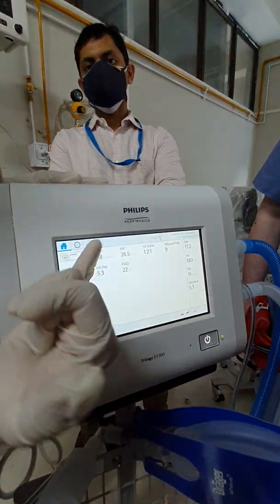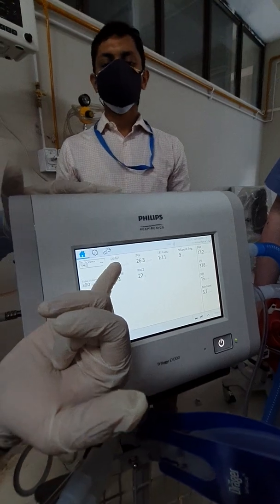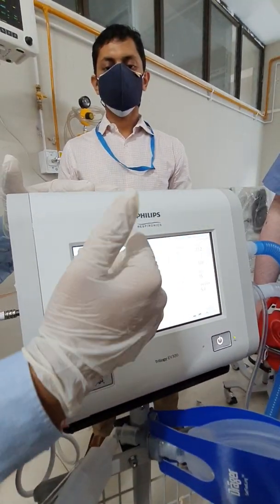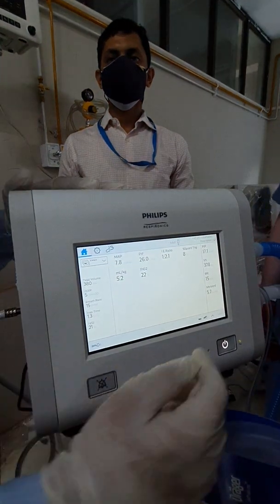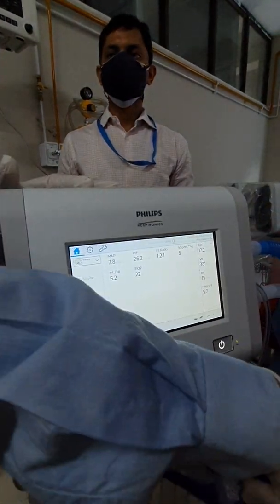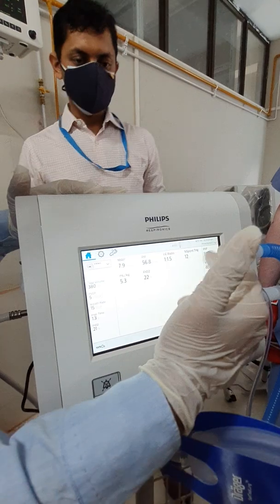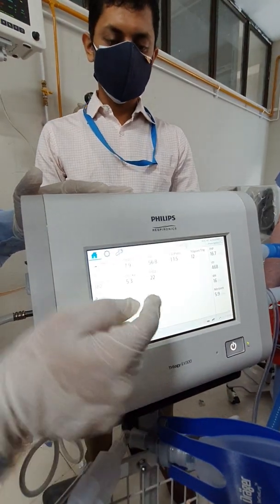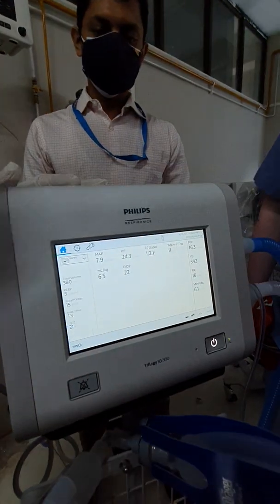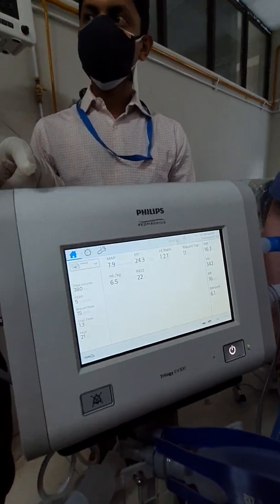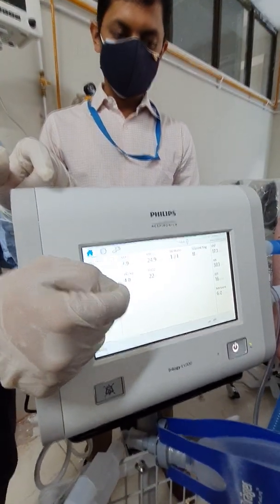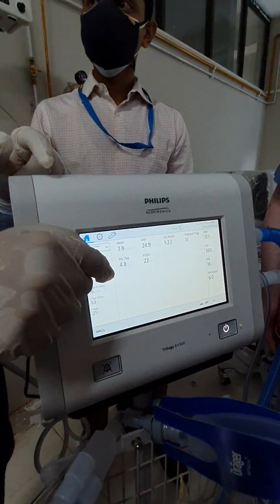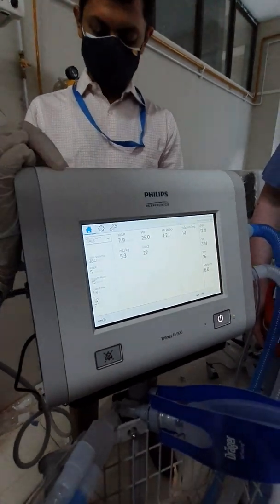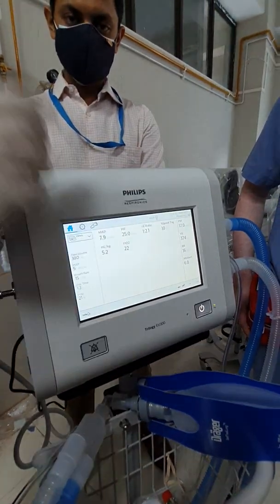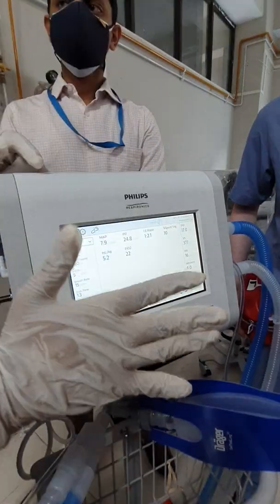Here you can see MAP, the mean airway pressure, peak flow, how it is generating, I:E ratio, and what is coming from the patient, the spontaneous trigger. I did some triggering, so the activity will increase. This is ml per kg, so every breath you are going to get this value. This is very vital. We are set in volume control, and this is the percentage that you are going to measure.